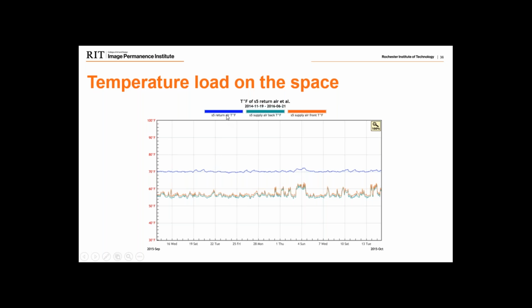So if you look at this data set, both the teal and the red lines are the supply for the space. Like I showed earlier, getting a data logger directly on the supply vents and directly at the return vents in the space, getting an idea for what's going into and out of a space. So here we're supplying about 56, 57 degrees for the collection space, but we're returning 70 degrees out of the collection space. First of all, from these two lines down here to up here is almost 14, 15 degrees that goes back and the mechanical system has to remove.